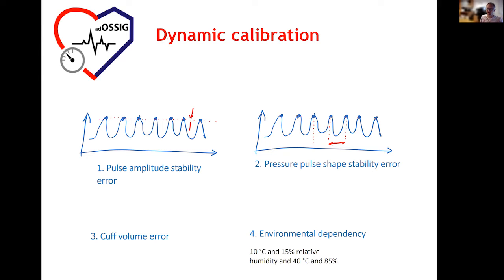So to put it more simply, if you want to dynamically calibrate the simulator, at least 4 stages should be done. The first part would be amplitude stability error. We would make the simulator output the same signals, and then we would evaluate how the maximum amplitude would change. Ideally, they would not change. The second one was cutting these pressure pulses into single pressure pulses and comparing the shapes. By putting all the pressure pulses together, we could see how the pressure pulse shape changes. Ideally, it should not change. All the pressure pulses should be the same.